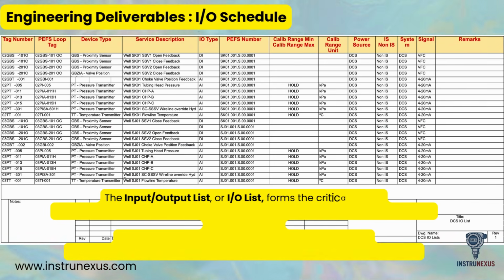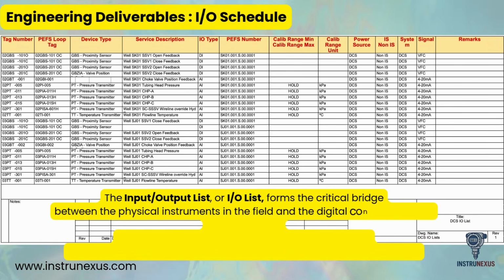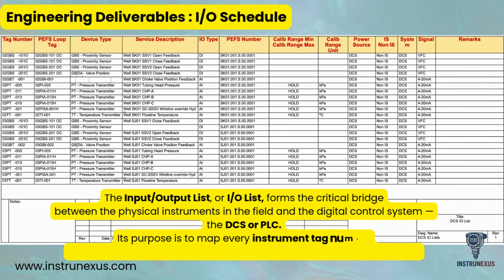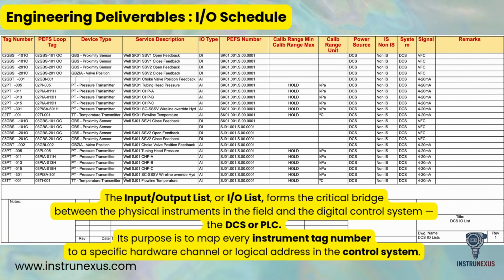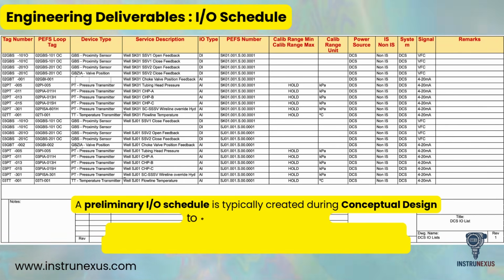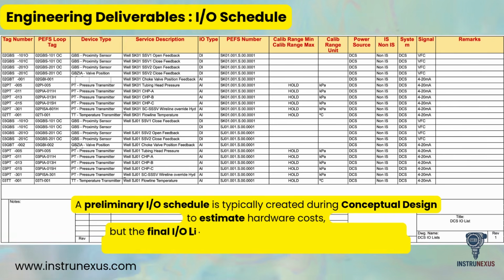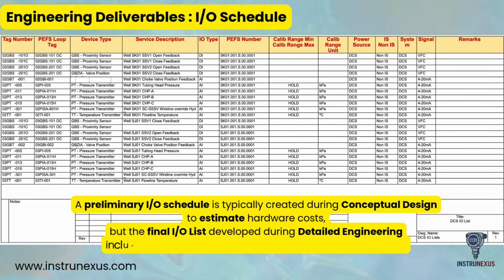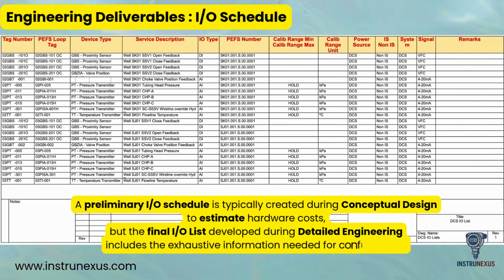The Input-Output List, or I/O list, forms the critical bridge between the physical instruments in the field and the digital control system, the DCS, or PLC. Its purpose is to map every instrument tag number to a specific hardware channel or logical address in the control system. A preliminary I/O schedule is typically created during conceptual design to estimate hardware costs, but the final I/O list developed during detailed engineering includes the exhaustive information needed for configuration.